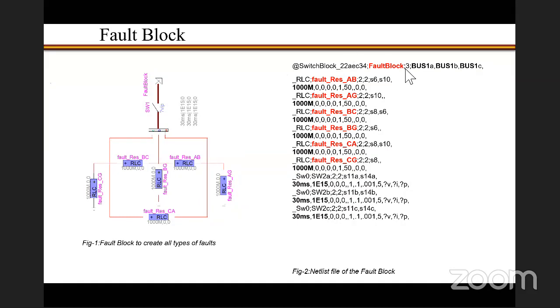For example, I put it here, bus 1A, 1B, 1C. That means A phase, B phase, C phase, all 3 phases should be there because this is a 3-phase network. So now if I change this bus 1 to bus 2, what you need to do is take the netlist file, search for this particular name, fault block. Then you will go to that particular code. And at that point, you just need to simply write bus 2 instead of bus 1. Then it will automatically create a fault at bus 2. And then you can see a lot of other things.